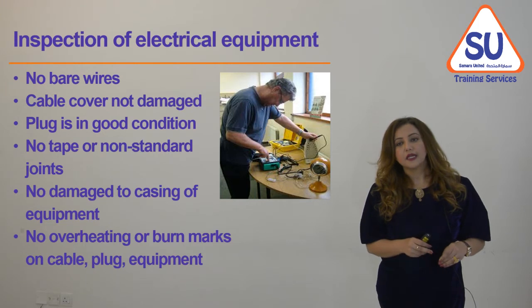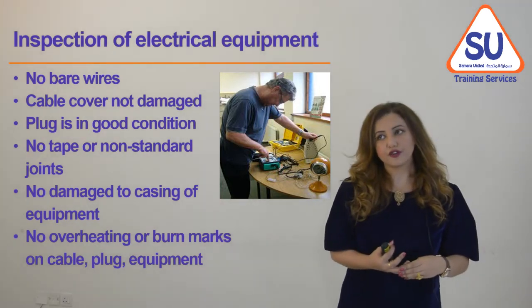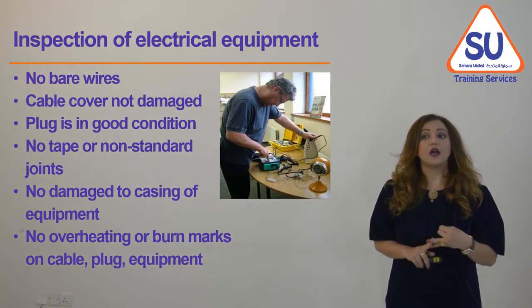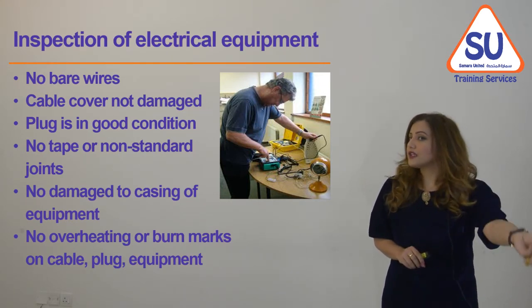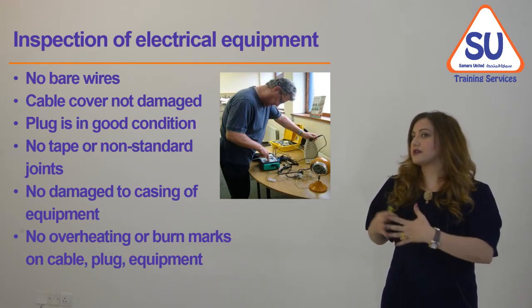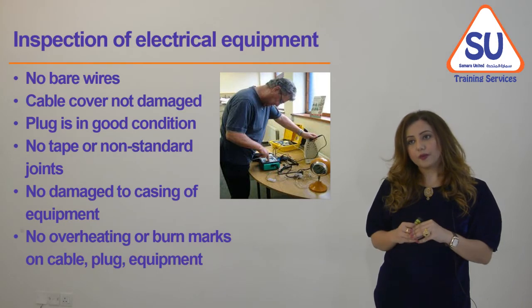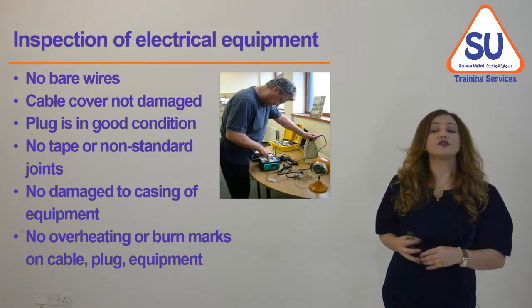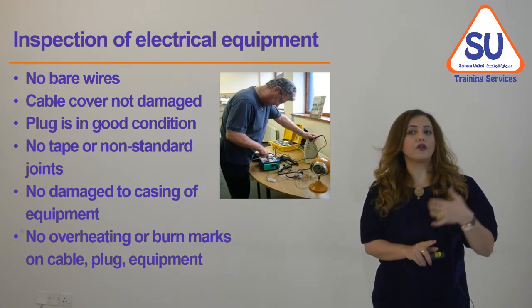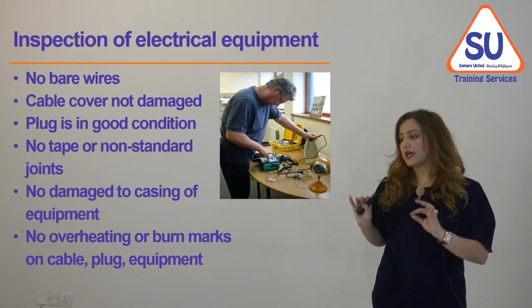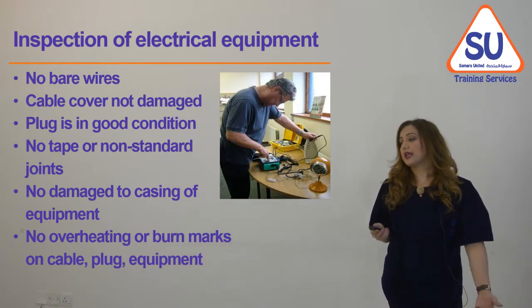For the inspection of electrical equipment, here is a simple checklist. We need to check that there are no bare wires, that cable covers are not damaged anywhere, that plugs are in good condition — plugs are often forgotten but are a main cause of failures and fires. Check there is no tape or non-standard joints in the equipment or cables, no damage or signs of damage to the casing, and no signs of overheating such as burn marks on cables, plugs, or the equipment. If any of these signs are noticed, do not use the equipment — take it for maintenance and checking before using it again, if it can be used again.